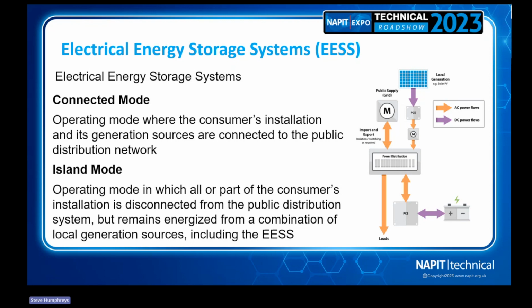When we talk about island mode, this is a mode where all or part of the consumer's installation is disconnected from the DNO. We haven't got a grid supply, okay? But certain parts of the installation can remain energized. So for instance, you could have a separate board for maintained loads. Generally everything else that's unimportant would go off, but you might choose to keep a freezer socket on, a Wi-Fi connection, perhaps some landing light in a domestic situation. It's not going to last forever off the battery, but it should be able to keep that property going until the mains is restored. So that's what we mean by islanding mode.